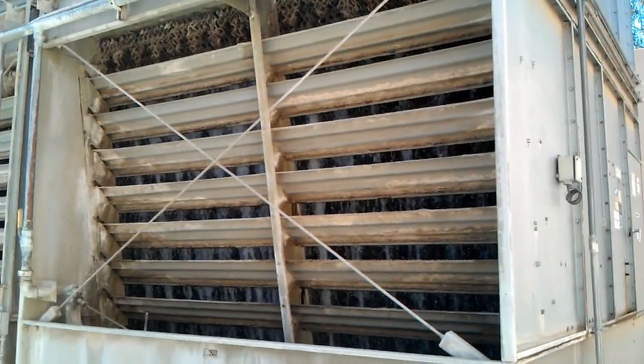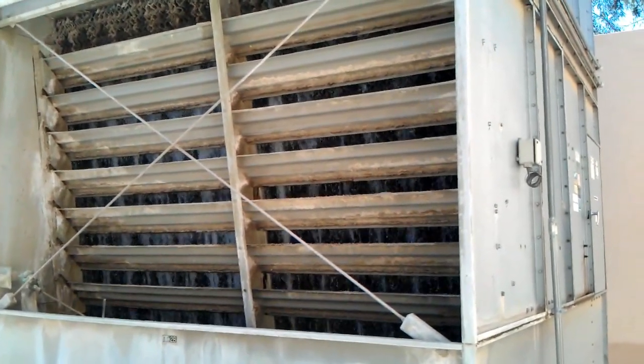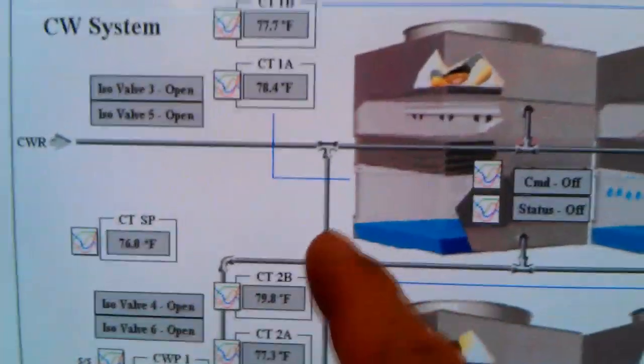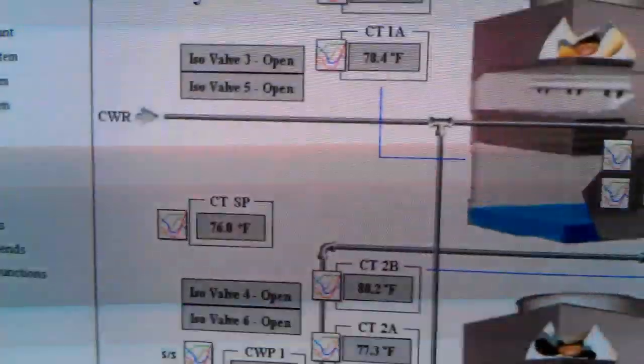So this is one refrigeration process right here. I'll go to the chiller to show you the temperature. We've got water coming from the chiller over 80 degrees, evaporating — we've got two fans stopped right now. Pretty mild day because it's 96. And the net water temperature is dropping down to 78 degrees.